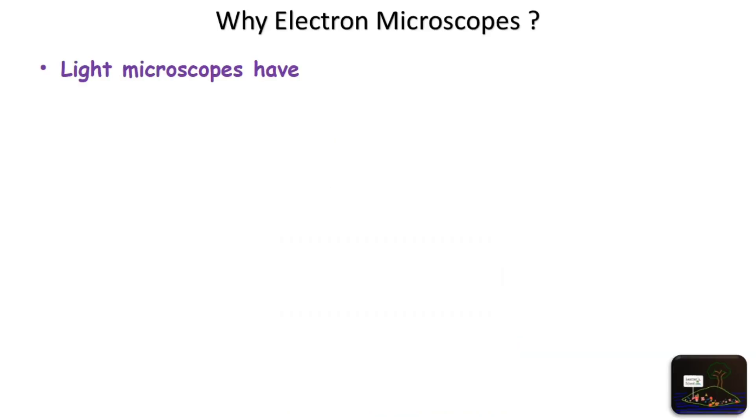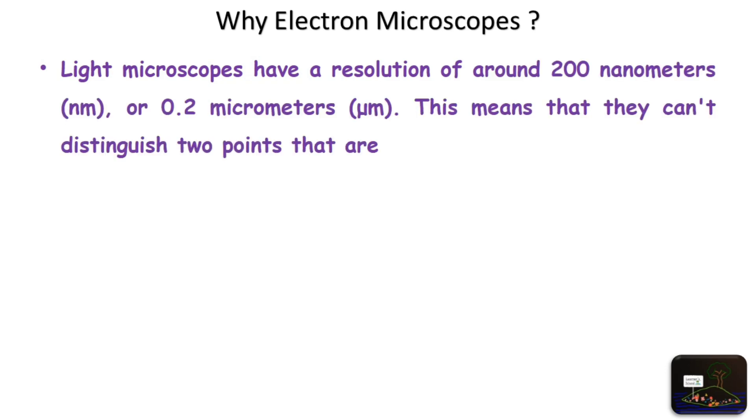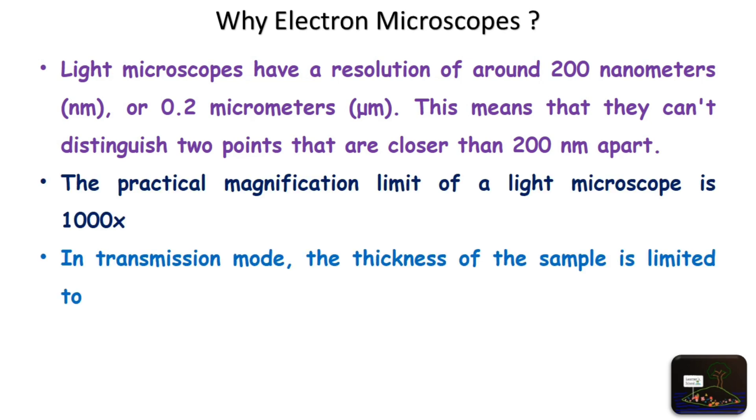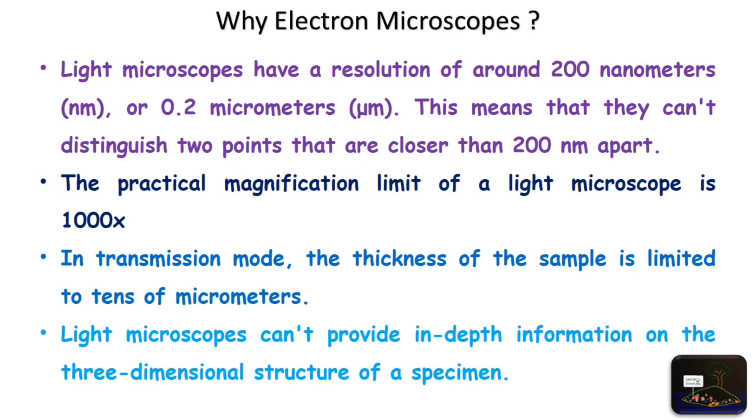Light microscope has resolution of around 200 nanometers, or 0.2 micrometers. This means, they can't distinguish two points that are closer than 200 nanometers apart. The practical magnification limit of a light microscope is 1000x. In transmission mode, the thickness of the sample is limited to tens of micrometers. Light microscopes cannot provide in-depth information on the three-dimensional structure of specimen.